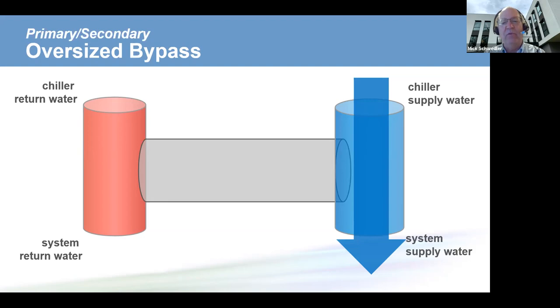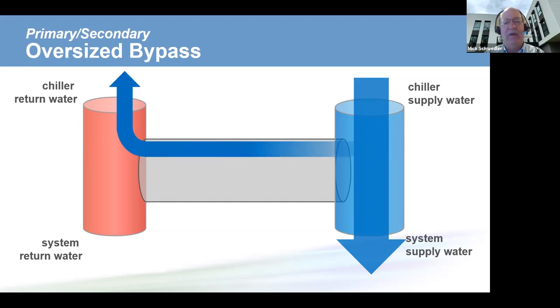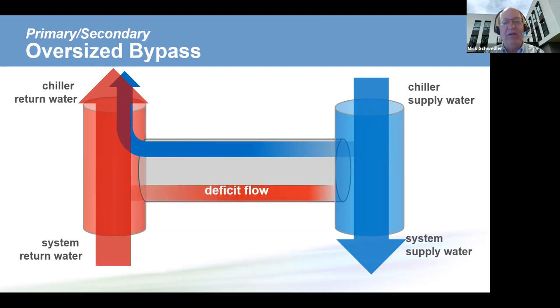But what happens is when the water gets here, water flows from high pressure to low pressure. And it gets here and it sees this really low pressure drop because the bypass line is so big. So some of the chilled water, instead of going out to the system, actually goes this way in the bypass line. Well, on the return side, the same thing happens. We have warm return water coming from our coils. Some of it, rather than going back to the chillers, sees this very low pressure drop and flows this direction in the bypass line.